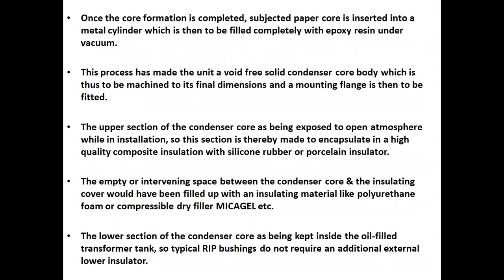Once the core formation is completed, the paper core is inserted into a metal cylinder, which is then filled completely with epoxy resin under vacuum. This process makes the unit a void-free solid condenser core body, which is then machined to its final dimensions, and a mounting flange is fitted.